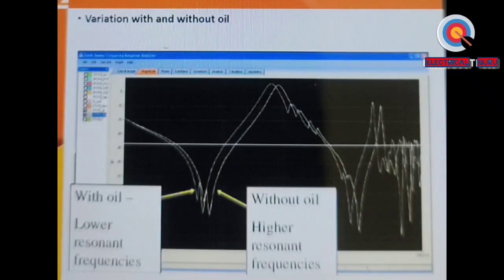Now, as I told you, nowadays there is a practice that for large transformers, before shipment and after loading on the trailer, we carry out SFRA, because at that time it is without oil. When it arrives at site, obviously you cannot fill oil in it, so you will also perform tests without oil. So a reference signature of the transformer is taken without oil, and after you install it on the plinth and fill up oil, obviously you want to have a reference signature for the fully oil-filled transformer.